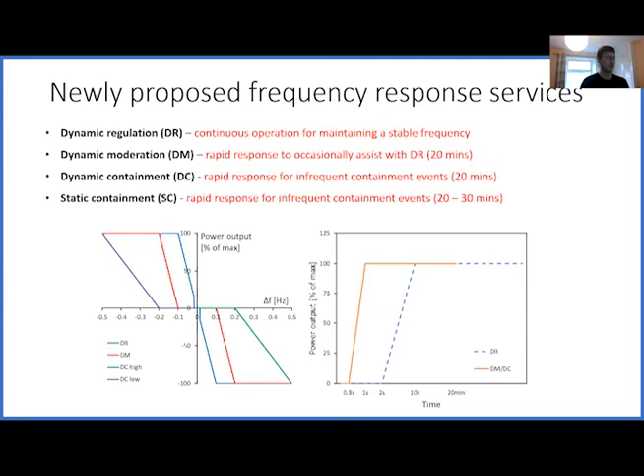With dynamic regulation, it has to respond as soon as the frequency goes outside of the small deadband, and be at maximum response by plus or minus 0.1 Hertz. And on the right, you can see this is about the response speed. Dynamic regulation doesn't have to be that fast. Delay time of 2 seconds and full response by 10 seconds, a bit like primary in the traditional services.